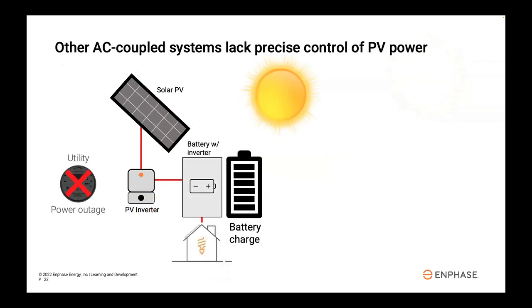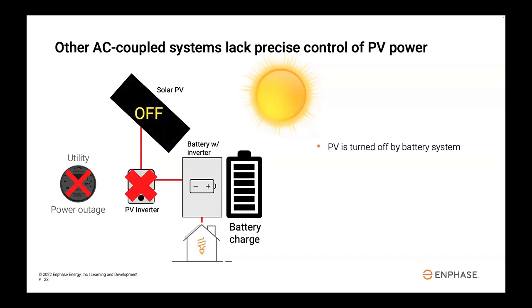Let's compare that to AC coupled systems and how they handle it. Basically, AC coupled systems, in order to curtail solar power, send a crude signal to the solar inverter called a frequency shift. It tricks the solar inverter into thinking there's an unstable grid, forcing it to shut off completely. The problem with this approach is that with the solar system off, the battery is now the sole source of power, and it's going to begin to drain.